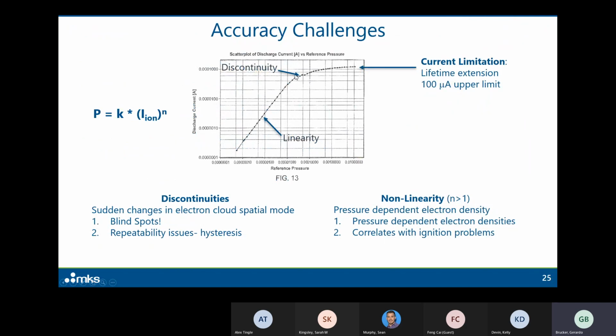So particularly in this area here, you really don't have a good way to calculate pressure if you get a step down in the ionization. So a well-designed cold cathode gauge needs to have a lot of linearity, and it has to have no discontinuities. Also, non-linearity relates to ignition problems. Often, if your linearity is no good, your ignition pressure is also much higher, and you can run into trouble. For those of you looking at why this curve turns around, you always put a limit on the amount of current that can flow in a cold cathode gauge so that it doesn't sputter itself away.